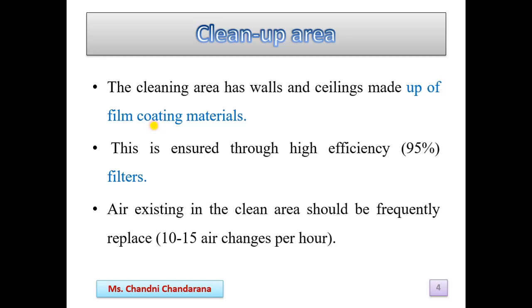This is a requirement for aseptic processing. This is ensured through a high efficiency filter — the air is filtered and there should be 95% pure air. Air existing in the clean area should be frequently replaced, and the frequency is 10 to 15 air changes per hour. This is the cleanup area.